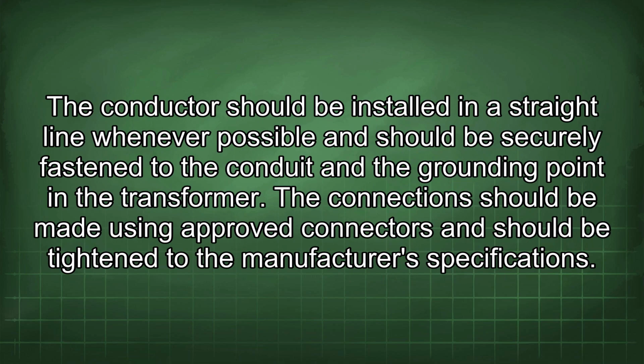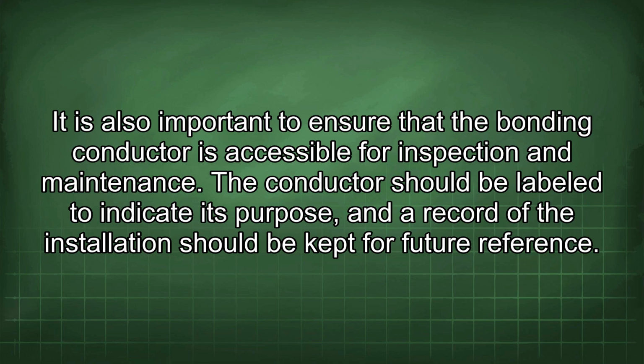The conductor should be installed in a straight line whenever possible and should be securely fastened to the conduit and the grounding point in the transformer. The connections should be made using approved connectors and should be tightened to the manufacturer's specifications. It is also important to ensure that the bonding conductor is accessible for inspection and maintenance. The conductor should be labeled to indicate its purpose, and a record of the installation should be kept for future reference.